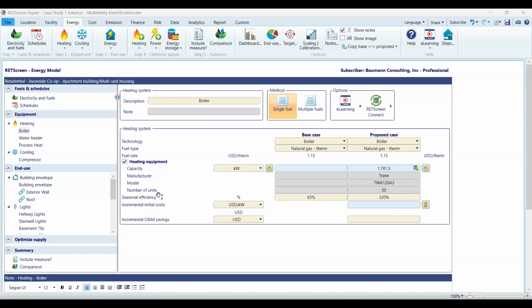What's next? We have a cooling COP of 6. So let's go back to RETScreen. Oh sorry, I did forget to mention that you have to change your technology and fuel type from boiler to heat pump. And heat pump is not going to use natural gas, it's going to use electricity. So you change the fuel source to electricity, and that's what your proposed case is for the heating system.